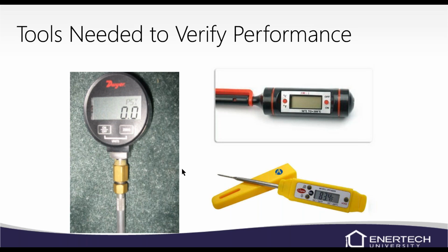We have some small units, half ton, and they'll have half pound pressure drop, maybe 1 pound at the most. And so that's really hard to see on an analog dial gauge. So that's why we do recommend the digital pressure gauge.